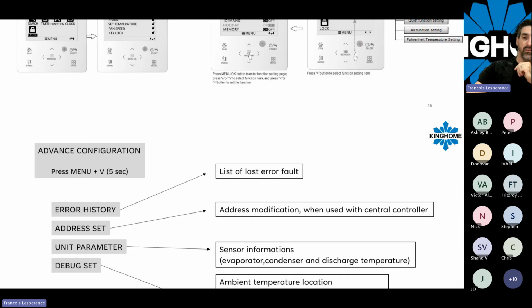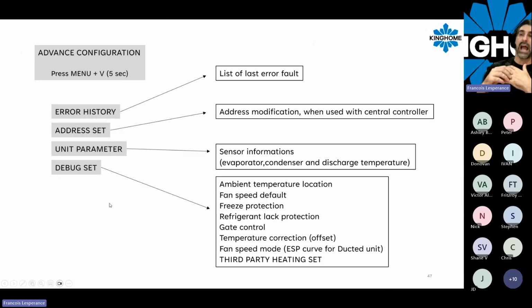And the thing that was added for Kinghome now is the advanced configuration. So if you push the menu and the arrow down at the same time for 5 seconds, you will enter a new configuration menu. So now you can look up the error history, the last error or a list of the last errors the unit has in its memory. Also, you can change the address of the system in case you have multiple wired thermostats connected to a central controller. Now you can set up the address of each one.